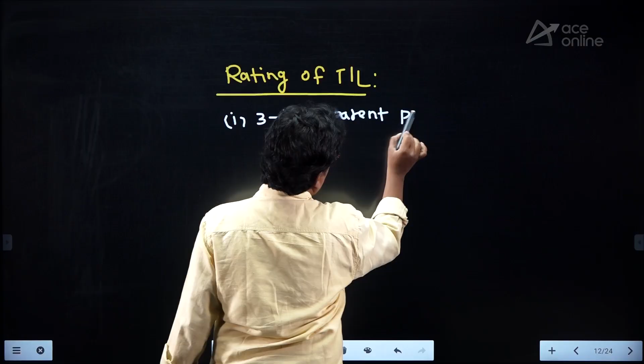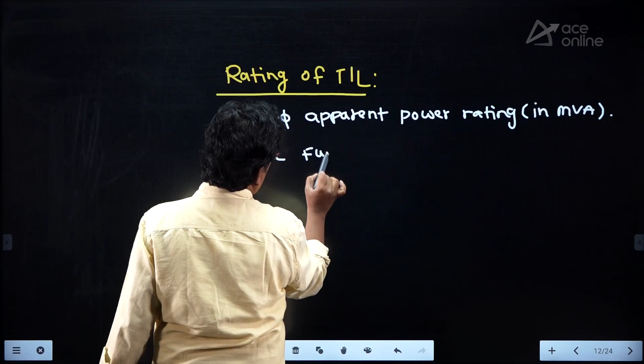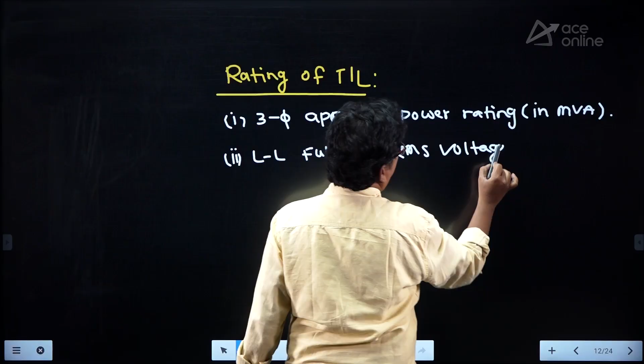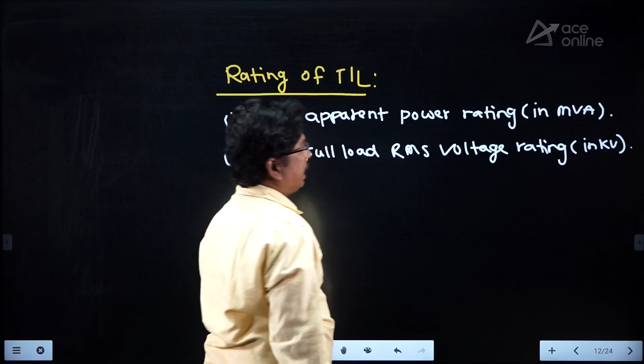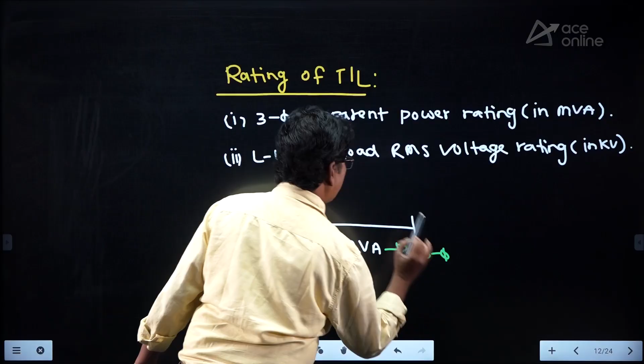And coming to the next element, transmission line, rating of the transmission line. In case of the transmission line, same 3-phase apparent power rating in MVA, and second one is line to line full load RMS voltage rating. It should be given in kilovolts, right? So if they say it is 100 MVA, that is the 3-phase apparent power rating, and suppose they say it is a 66 kilovolt transmission line. For a 66 kilovolt transmission line, this is the full load line voltage.